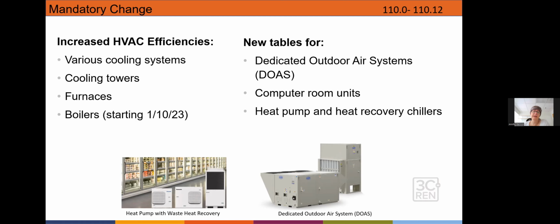Those dedicated outdoor air systems, the reason that's been put into the code is we're seeing a lot of projects now being designed for ductless heat pump systems. And in order to meet all our fresh outdoor air requirements, they're needing dedicated outdoor air systems to provide that ventilation air. So that's another category now that needs to be looked at.